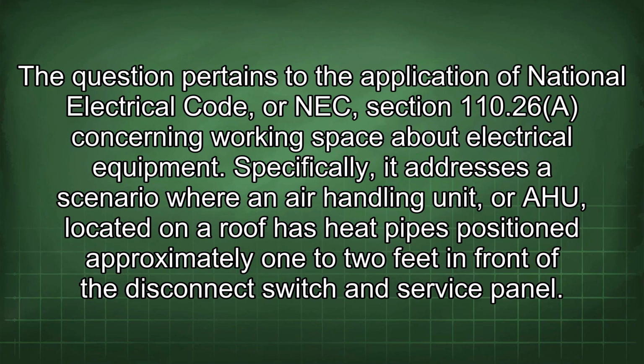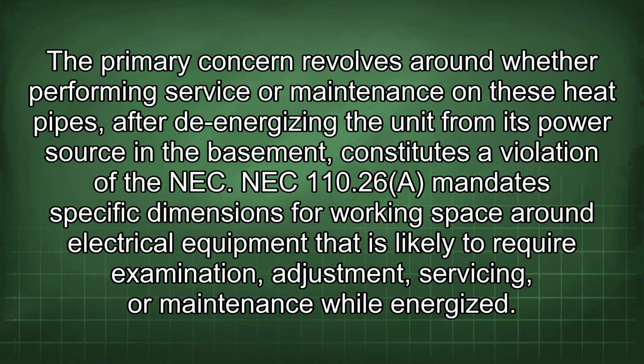The question pertains to the application of National Electrical Code, or NEC, Section 110.26 concerning working space about electrical equipment. Specifically, it addresses a scenario where an air handling unit, or AHU, located on a roof has heat pipes positioned approximately 1 to 2 feet in front of the disconnect switch and service panel. The primary concern revolves around whether performing service or maintenance on these heat pipes after de-energizing the unit from its power source in the basement constitutes a violation of the NEC.